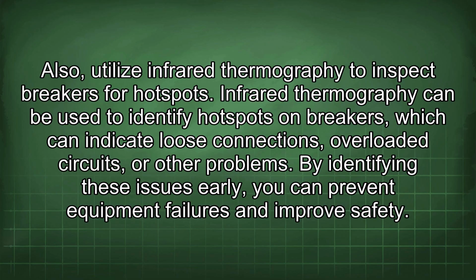Also, utilize infrared thermography to inspect breakers for hotspots. Infrared thermography can be used to identify hotspots on breakers, which can indicate loose connections, overloaded circuits, or other problems. By identifying these issues early, you can prevent equipment failures and improve safety.